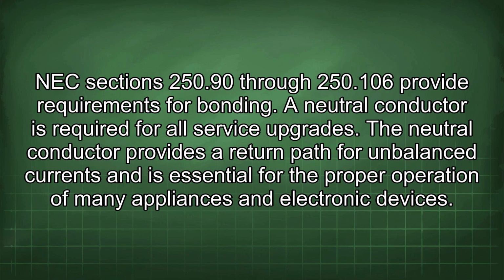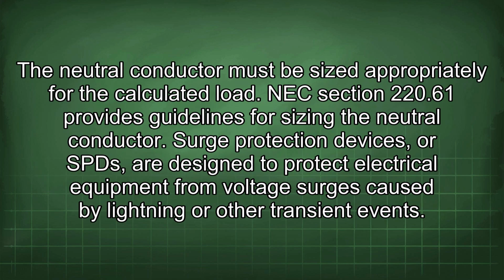A neutral conductor is required for all service upgrades. The neutral conductor provides a return path for unbalanced currents and is essential for the proper operation of many appliances and electronic devices. The neutral conductor must be sized appropriately for the calculated load. NEC section 220.61 provides guidelines for sizing the neutral conductor.